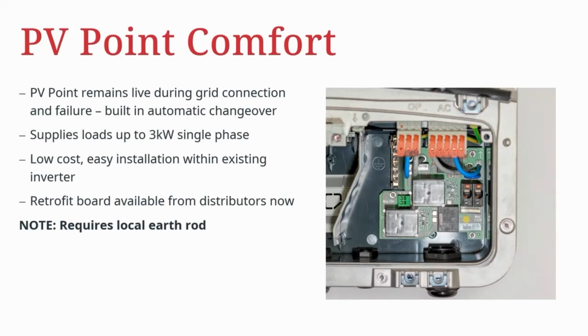This enables the PV point circuit to remain live during a grid failure, but also in normal AC grid connection mode, meaning that you no longer have to switch devices off and reconnect them in the event of a grid failure. Retrofittable board can be purchased from Fronius distributors and installed easily within the inverter. Again, we need to have that local earth rod within the property and also a local RCD for those circuits connected to the PV point comfort device.